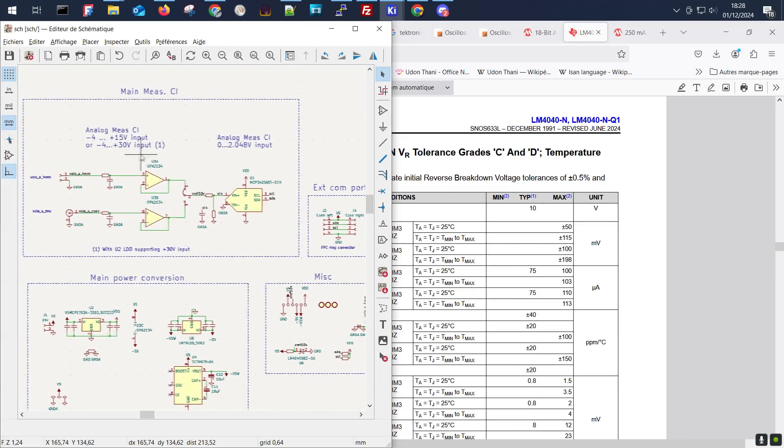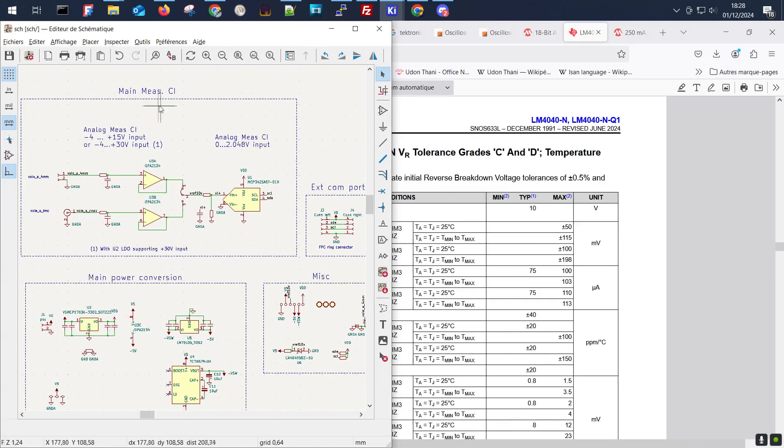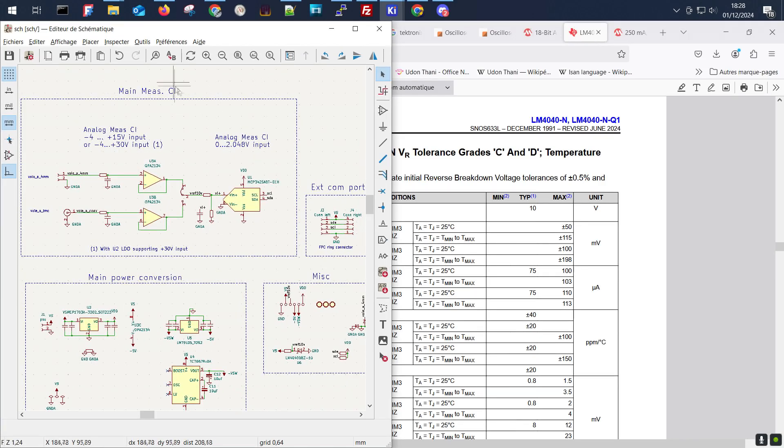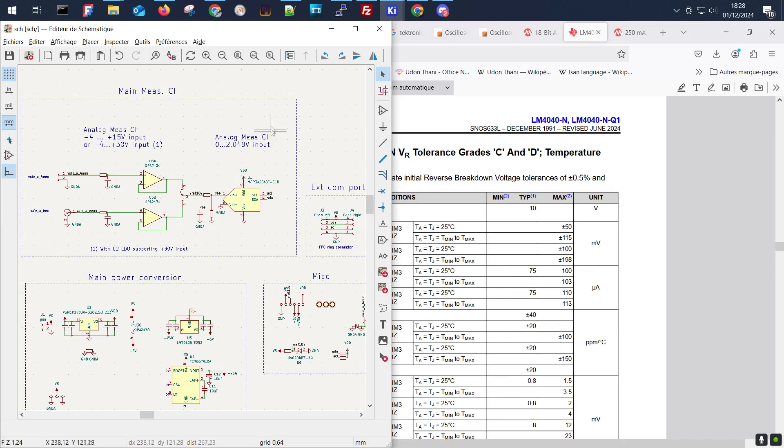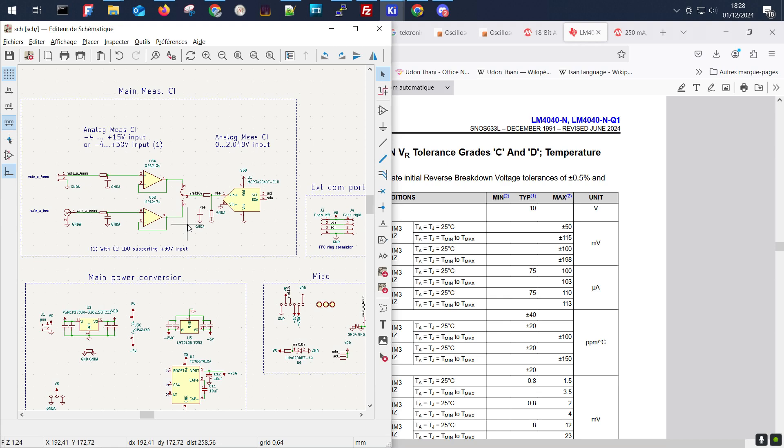We actually have a minus VSW which is our supply voltage regulated down to minus 5 volts. So we will use this reference up to say 15 volts DC inputs to calibrate our instrumentation with a clean 10 volt reference.